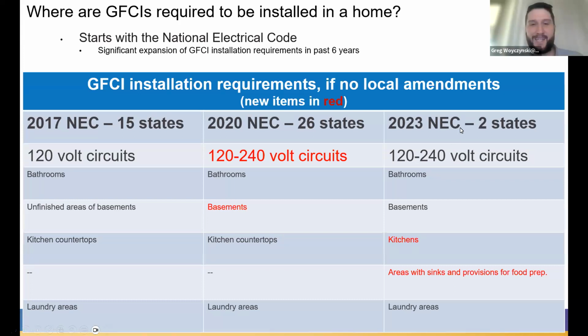Then in the 2023 NEC, again, a push from GFCI manufacturers to expand the requirements to install these devices. We see probably the biggest expansion is kitchens. So if your state has adopted the 2023 NEC without amendments, every receptacle in the kitchen must be GFCI protected. So your oven, your microwave, all your countertop appliances must be connected to either that GFCI receptacle or a regular receptacle that feeds back to a GFCI breaker. So this is a big change, and I think this is a lot of the root cause that's causing heartburn out there today for new constructions.